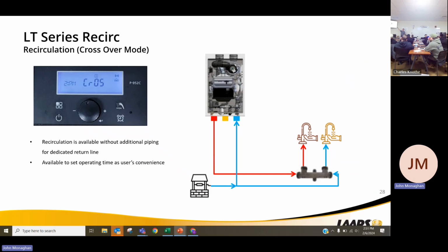You're going to set your control to tell it that it is in the crossover mode, so the control knows that it's not going to be getting hot water back. It's basically going to just push the water into the cold side. You're going to leave the domestic side capped. One of the advantages to this, yes, you get hot water faster. You don't have to run an extra line anywhere.